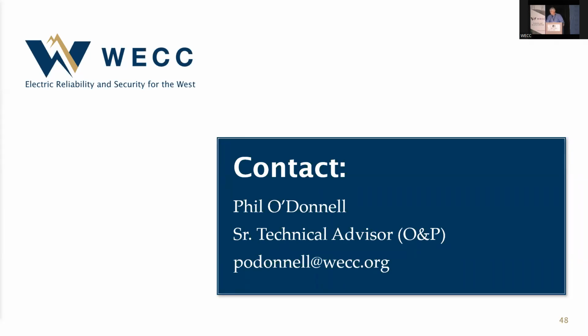Great. See a couple more here. I think we should have time for most of them. If a GO defines their point of demarcation in conjunction with the TO where the handoff occurs at the high side of the GSU, is the GO still required to rate the elements to the bus as you showed in your slides? No, as long as the GO doesn't own equipment beyond that point.